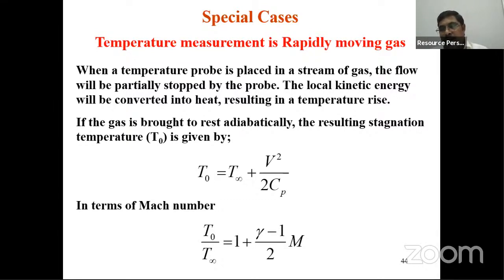You cannot simply keep a thermocouple there and measure the temperature. What will happen if we keep any thermocouple or temperature measuring device in the presence of a high speed stream? When you introduce any object or obstruction, within its vicinity the flow will become stagnant, because the flow will adiabatically come to rest. So when the flow becomes stagnant, the kinetic energy associated with the velocity of the fluid will be converted into local enthalpy, giving a temperature rise. That means whatever temperature you are sensing from your temperature measuring device may not be accurate.